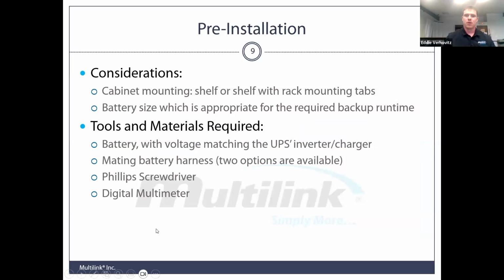With the introduction out of the way, we'll walk through some pre-installation steps. They're relatively simple. The Pantheon cell battery is itself one contained 48 volt or 36 volt package. It comes with a mating harness depending on the UPS you're using. When purchasing this battery, your major considerations are the cabinet it's mounting in and which size battery you select for the application. Most applications require an estimated runtime, anywhere from 2 to 4 hours depending on the wattage of the load. So the two major considerations are cabinet mounting and battery size.